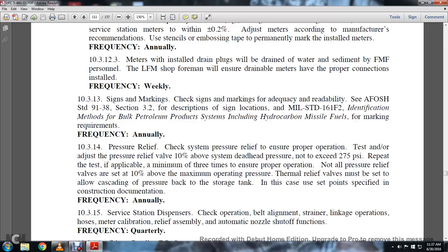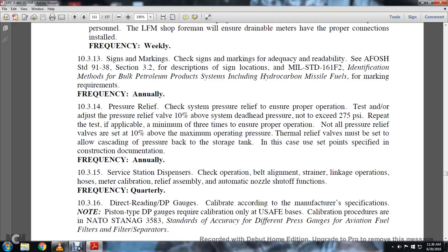Test the pressure relief at a value 10% above the system deadhead pressure, not exceeding 275 psi. Repeat the test a minimum of 3 times to ensure proper operation, if applicable. Not all pressure relief valves are set at 10% above the maximum operating pressure. Thermal relief valves must be set to allow cascading of the pressure back to the storage tank. In this case, use the set points specified in the construction documentation. Frequency: annually. The service station dispenser.